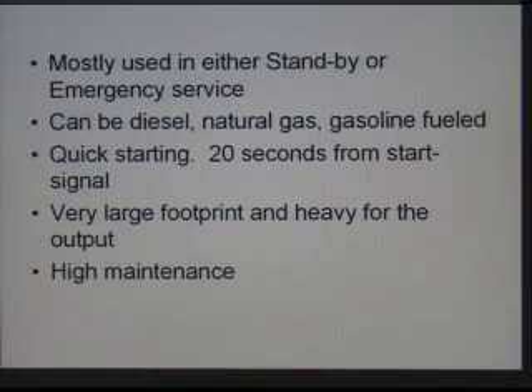Mostly they're used in standby and emergency service. They're not of a size that you would want to have for regular utility service. We buy engines in the 0.5 megawatt to the 5 megawatt range generally. And we put these into facilities that are kind of remote that may have power outages at any time. They're used to supply emergency power so that heating and ventilation takes place, and whatever emergency systems that the plant deems are necessary are allowed to continue running. Usually that will be the control systems for all of the equipment.